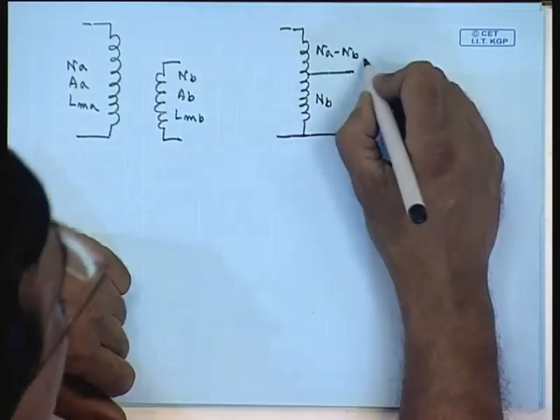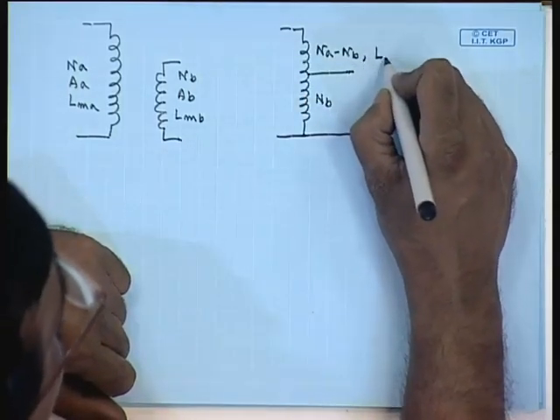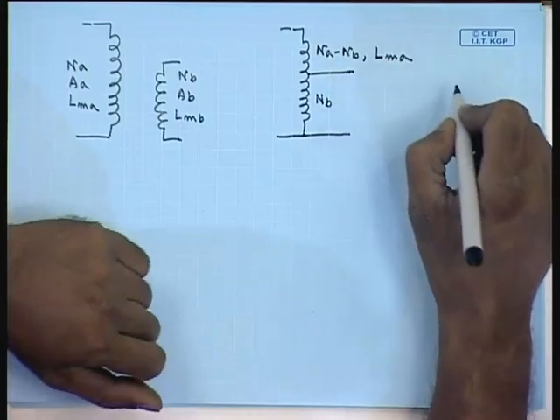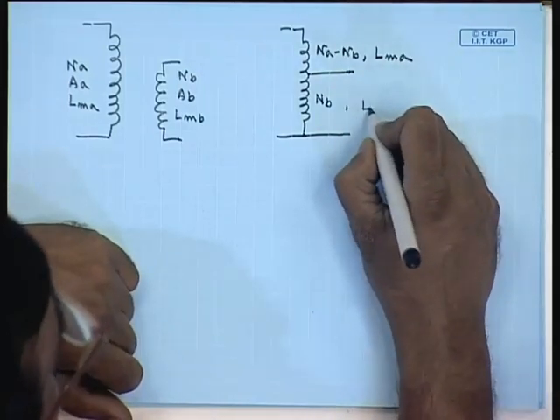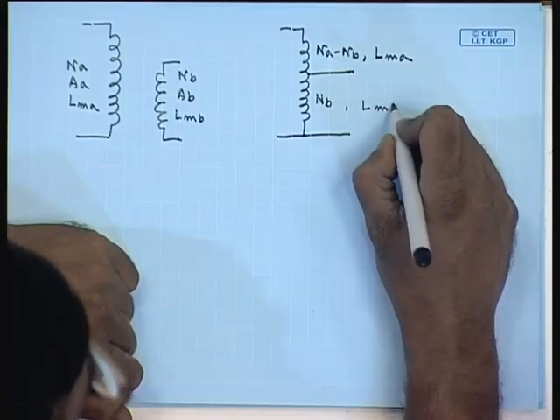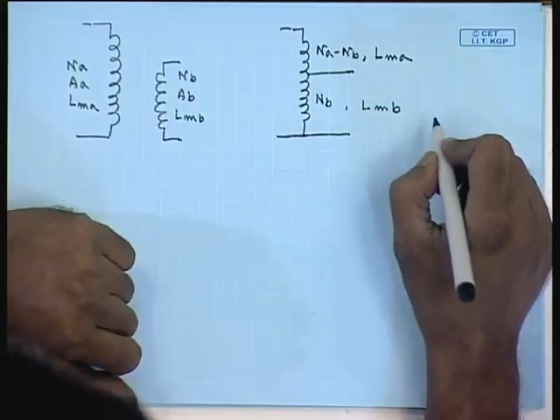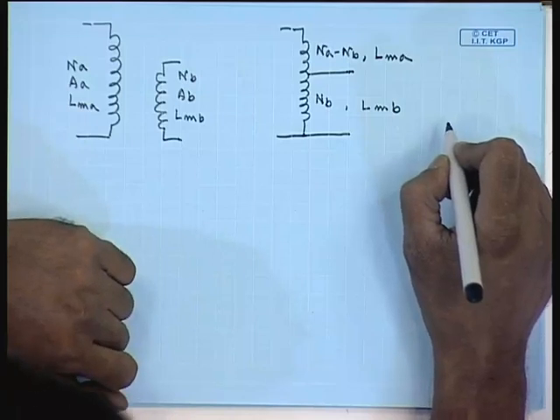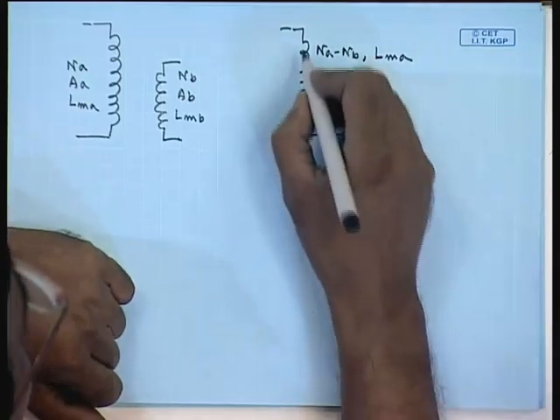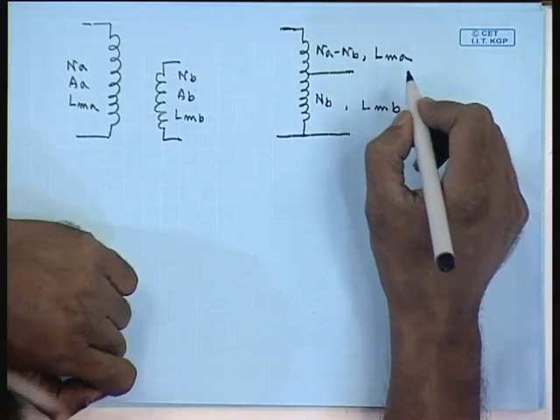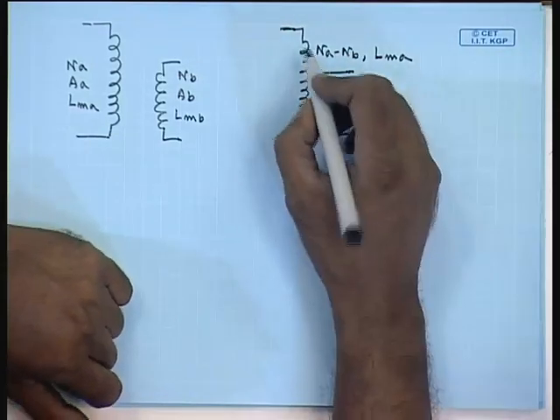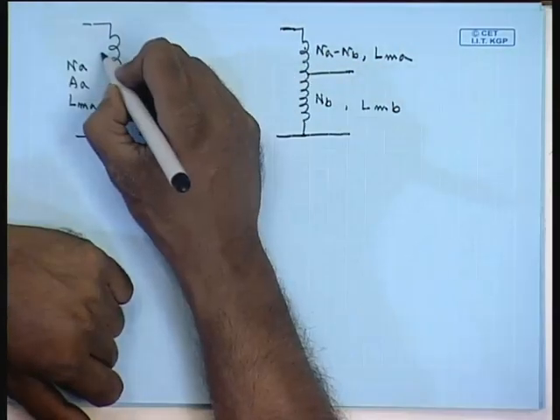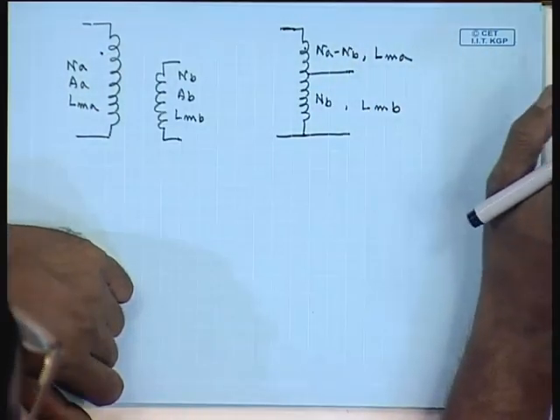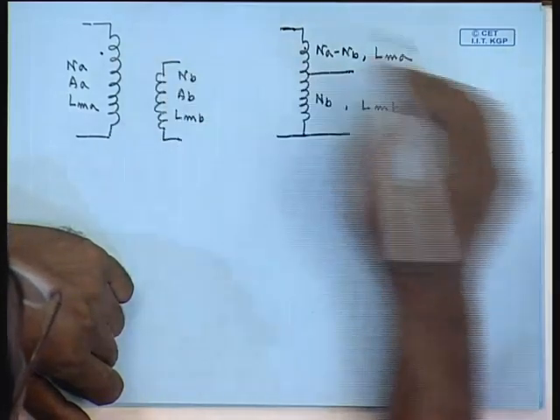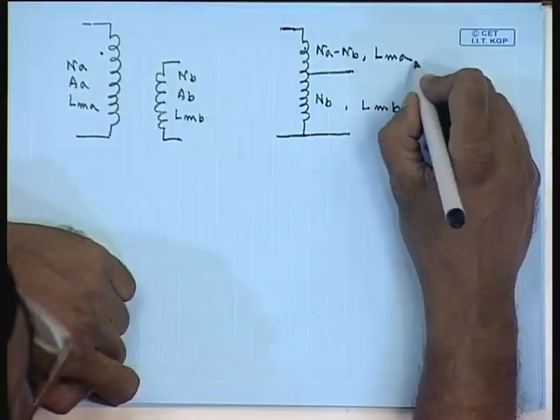Mean length of turn here, let us say still LMA, and here it is LMB. Now, let us consider the cross sectional area. This part of the auto transformer and the HV winding of the two winding transformer carries the same current if the two transformers have the same KVA rating. Therefore, their cross sectional areas should also be same.